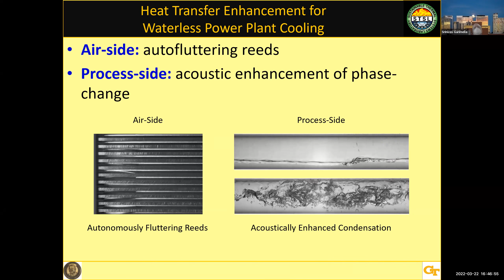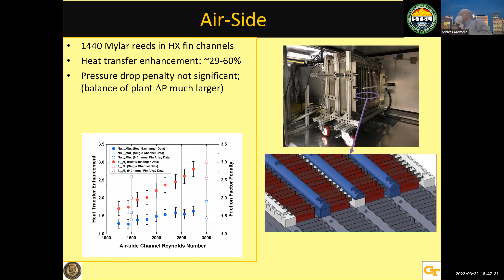So this is that technology. These are the fins of the heat exchanger, and these are the mylar reeds that are inserted, which cause that oscillation. We measured heat transfer enhancement of up to 60%, depending on conditions. Of course there's a pressure drop penalty too, but the pressure drop in the overall system is very large anyway compared to that in the simple heat exchanger core, whereas you're getting so much heat transfer enhancement.